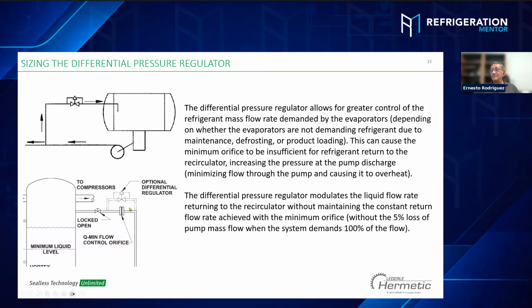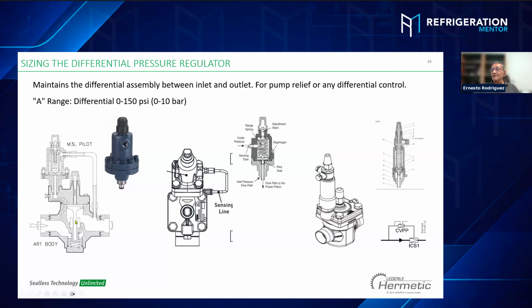Too many companies confuse them. A relief regulator is used when you have liquid trapped between the check valve and the shutoff valve, to relieve the gas that is building on the liquid. This is a relief regulator. Differential pressure regulator, I want to explain how the thing works. Okay, for example, these are different manufacturers, Hansen, Parker, and Danfoss. This side goes to the vessel, going to the recirculator, okay? And this is the pump discharge.